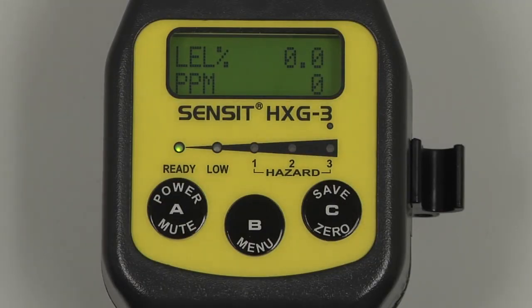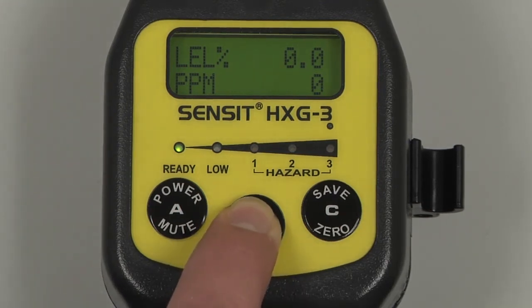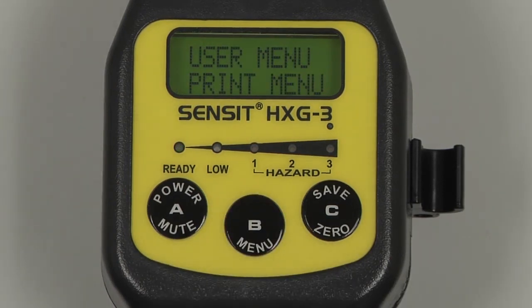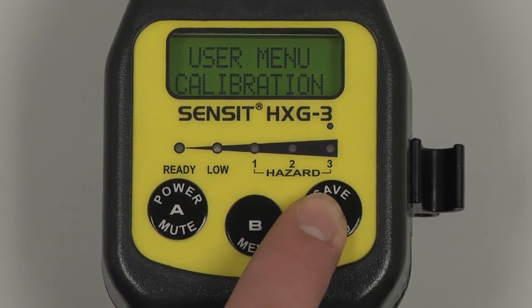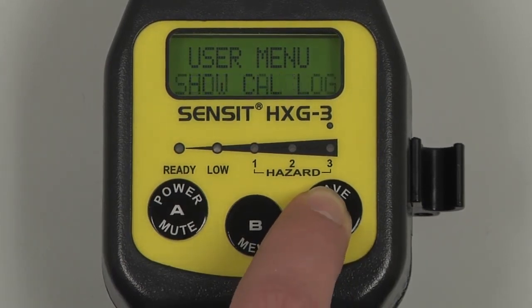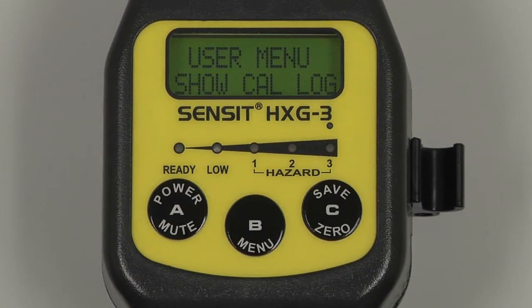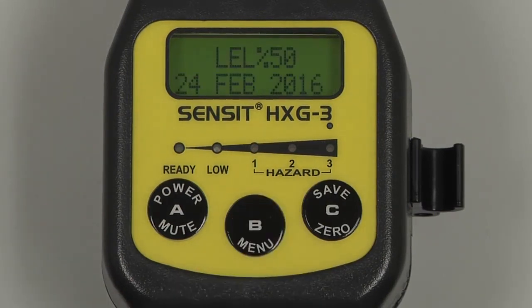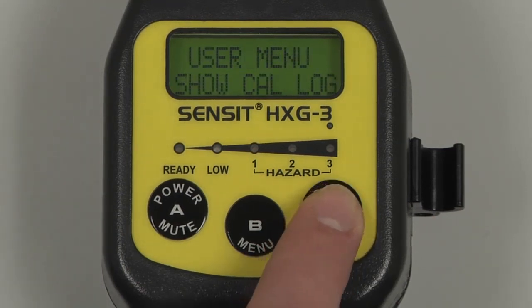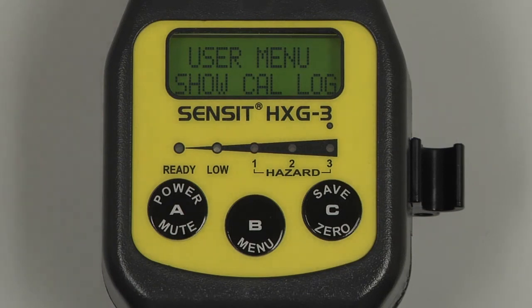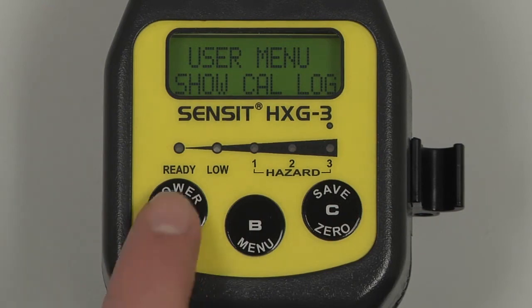To verify the calibration date, enter into the user menu by pressing and holding the B button, and scroll through the menu by pressing and releasing the C button until Show Cal Log appears. Select by pressing and releasing the B button, and we'll have a display for the calibration point and the most recent date that the instrument was calibrated. Pressing and releasing a button will return to the user menu. And we can return to the working display by pressing and releasing the A button.